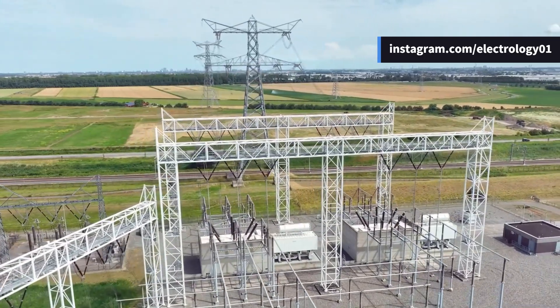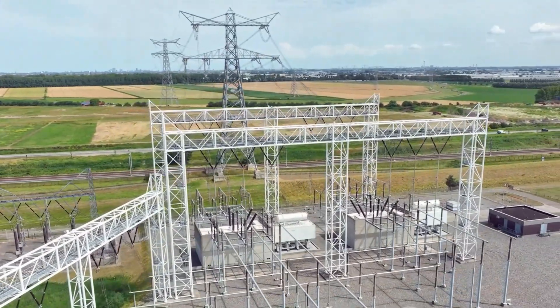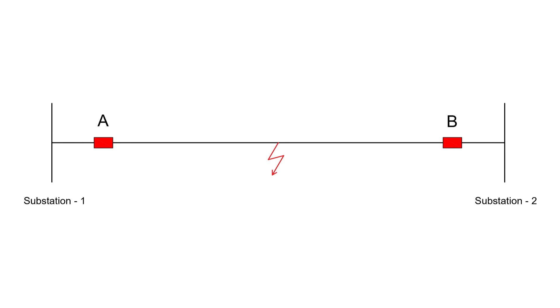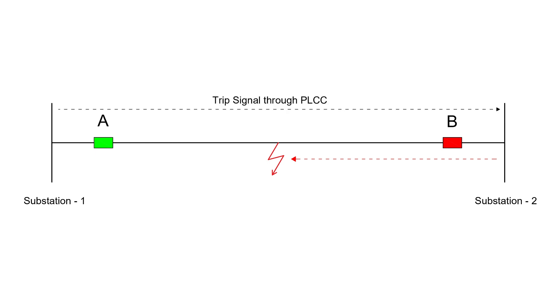Let's understand how this works in fault situations. Imagine a fault occurs in a transmission line. The relays at both ends — Station 1 and Station 2 — must trip their breakers to isolate the fault. But if only one breaker opens, the fault will not be fully cleared. In this situation, the relay at Station 1 detects the fault and sends a direct trip signal through the PLCC to the relay at Station 2.